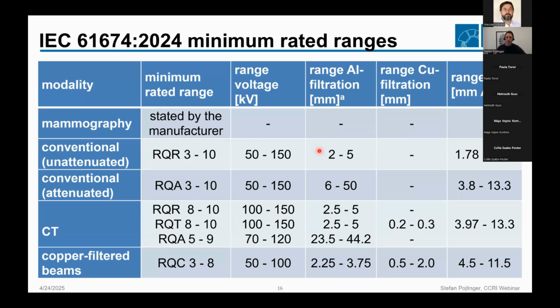The only thing that you can really say is if the XMM was tested against IEC 61674, which gives performance criteria for XMMs, there's a certain limit for the energy dependence. For example, if your XMM was tested for conventional beams in accordance with IEC 61674, then you can be sure that the energy dependence of the response will be less than 5% between RQR3 and 10, because this is a requirement put by the standard. So this is something you could ask in theory the manufacturer of the device. Was it tested and in which category? And then you have some knowledge about the energy dependence.